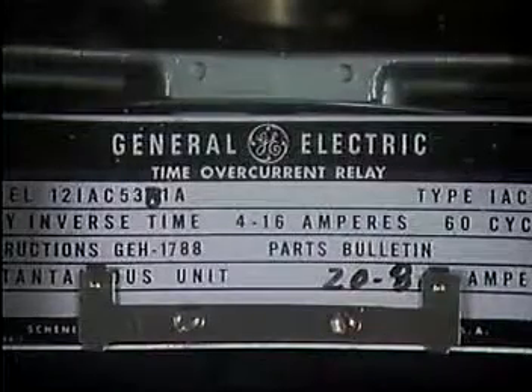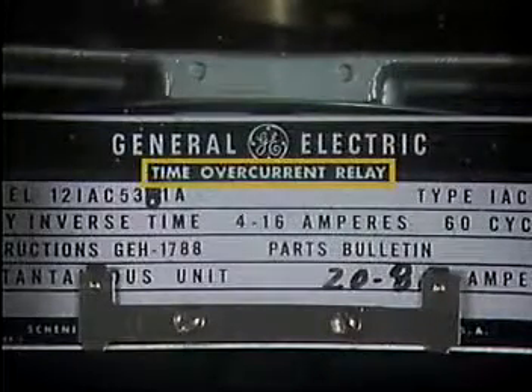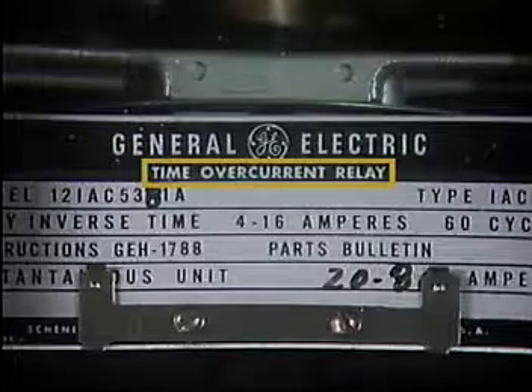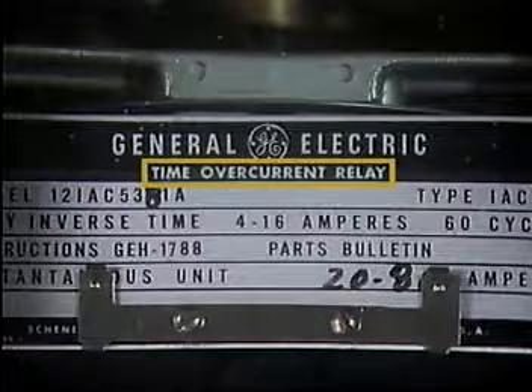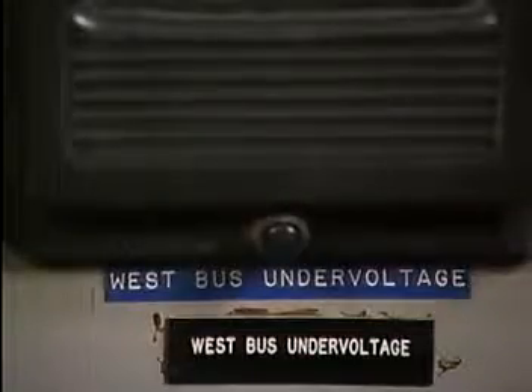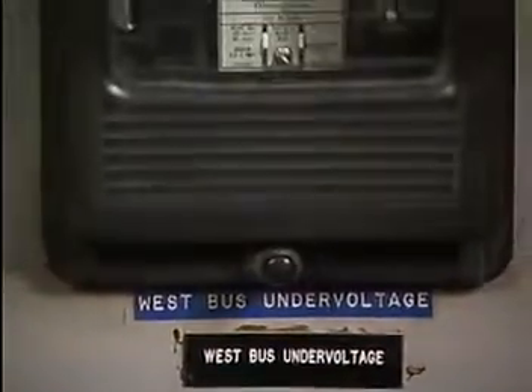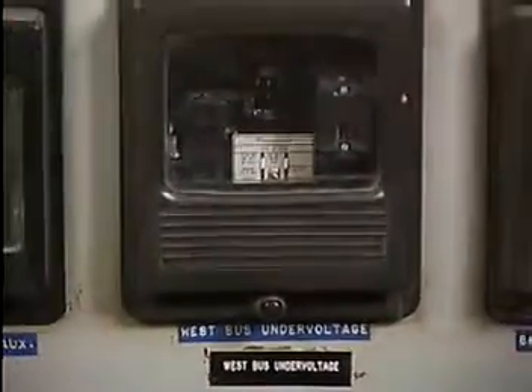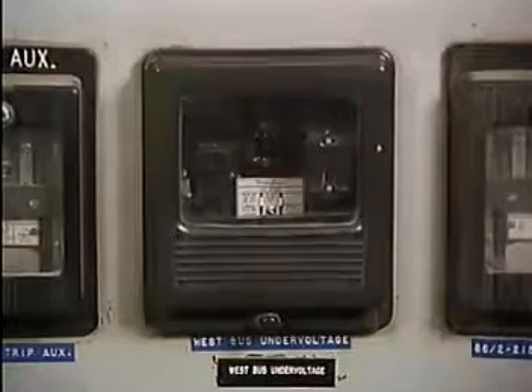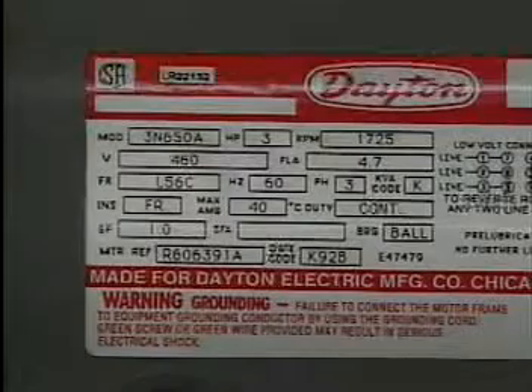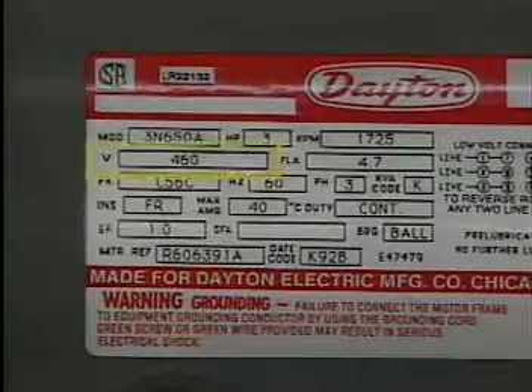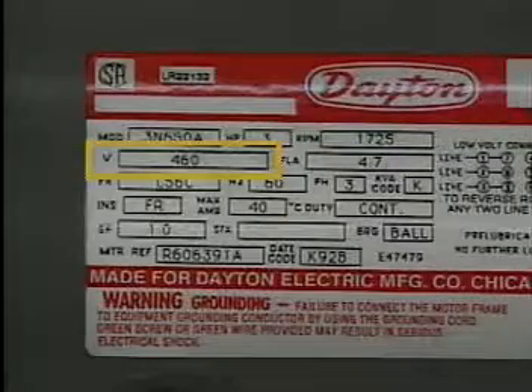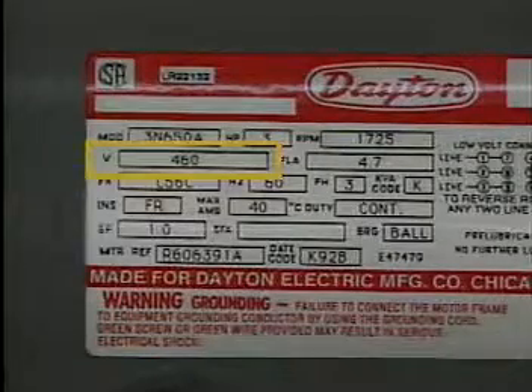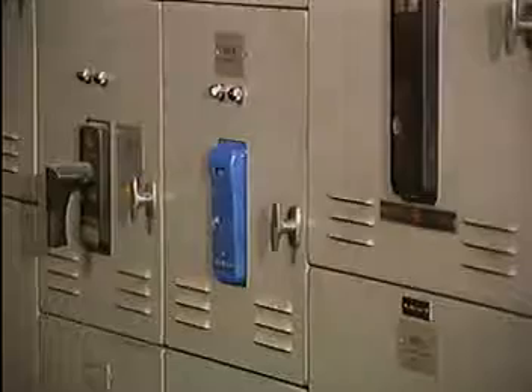One common type of relay is an overcurrent relay. Overcurrent relays protect equipment from damage caused by excessive current flow. Another type of relay, called an undervoltage relay, protects equipment from damage caused by lower than normal voltages. Motors and other equipment are normally rated for a certain voltage. Too little voltage can cause a dangerous increase in current flow.